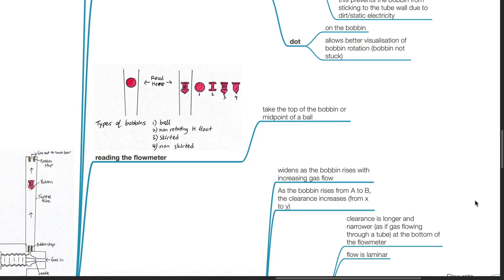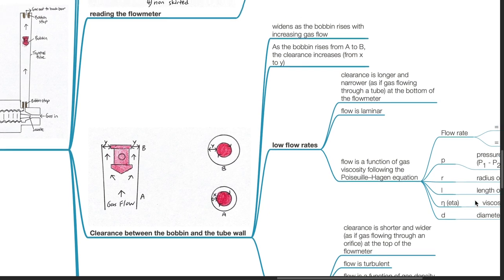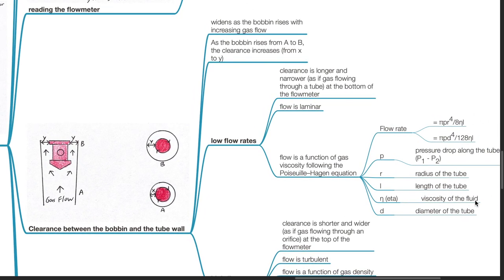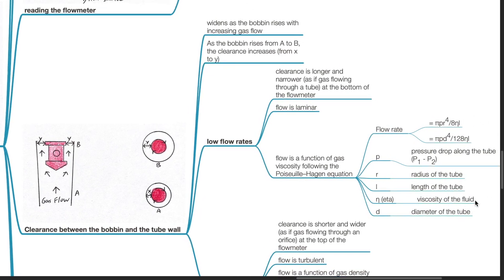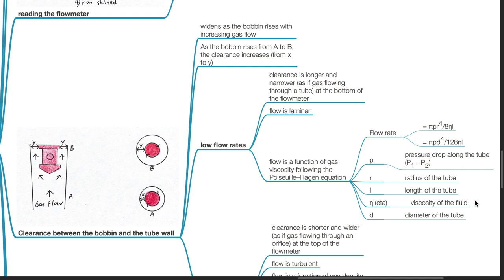Reading the flow meter: Take the top of the bobbin or midpoint of a ball. Clearance between the bobbin and the tube wall widens as the bobbin rises with increasing gas flow. As the bobbin rises from A to B, the clearance increases from X to Y.